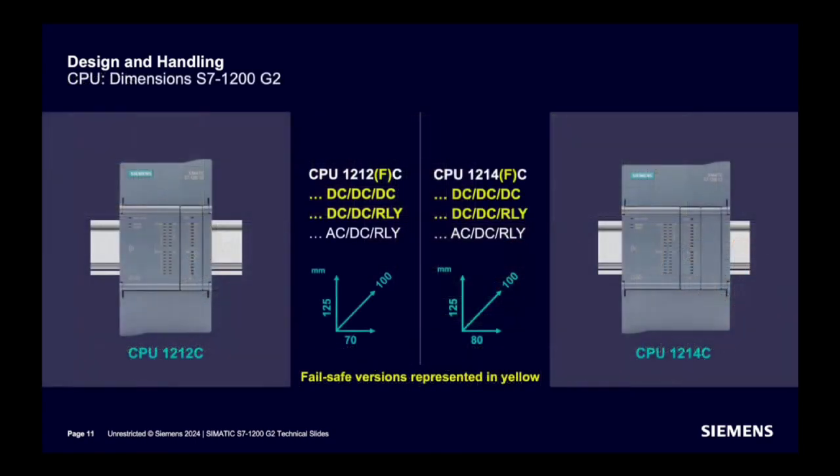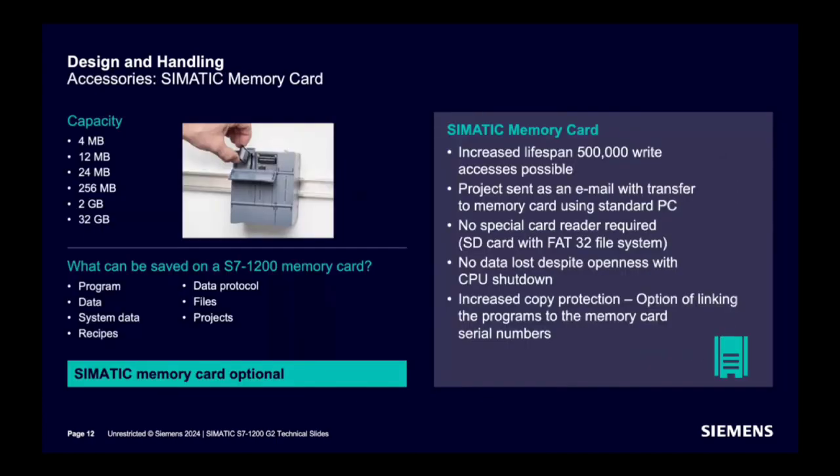Once more highlighting the design and handling of the CPU — dimensions are shown on the slide. Now, about the SIMATIC memory card for S7-1200: capacity options from 4 megabytes to 32 gigabytes are available. Program, data, system data, recipes, data protocols, files, and projects can be saved on the memory card. The lifespan of the memory card is increased to 500,000 write accesses. No special memory card reader is required, and increased copy protection by linking the memory card with the serial number of the CPU is supported. However, the memory card is not mandatory in an S7-1200 CPU.